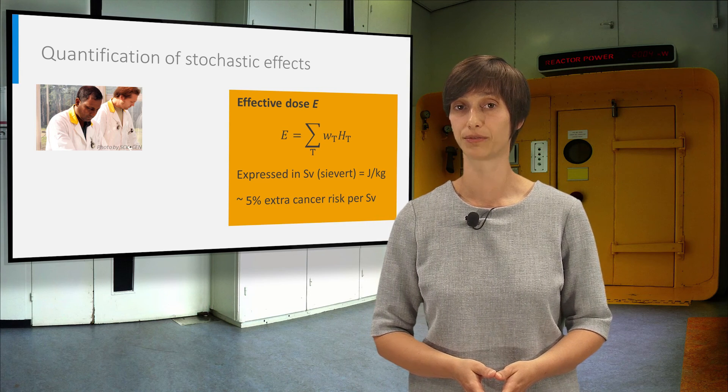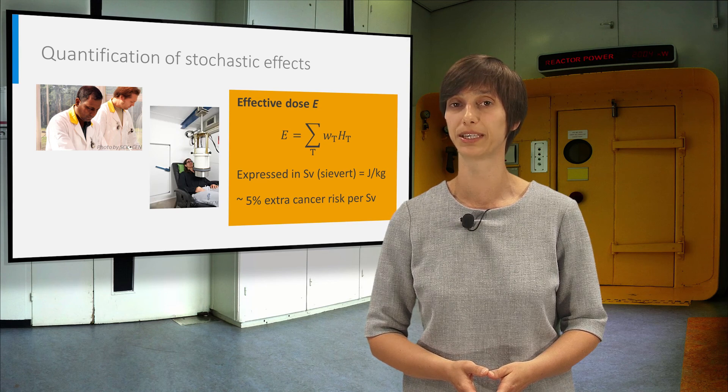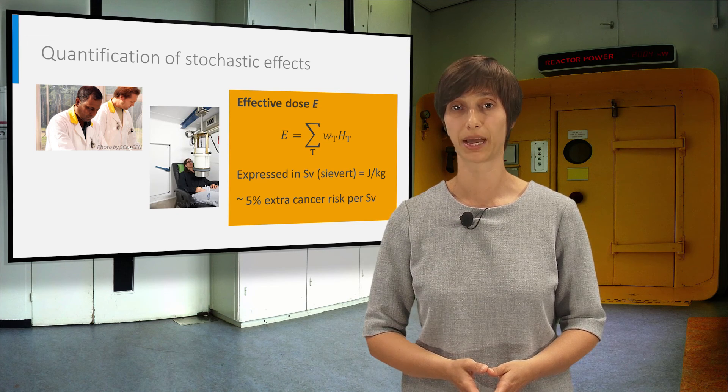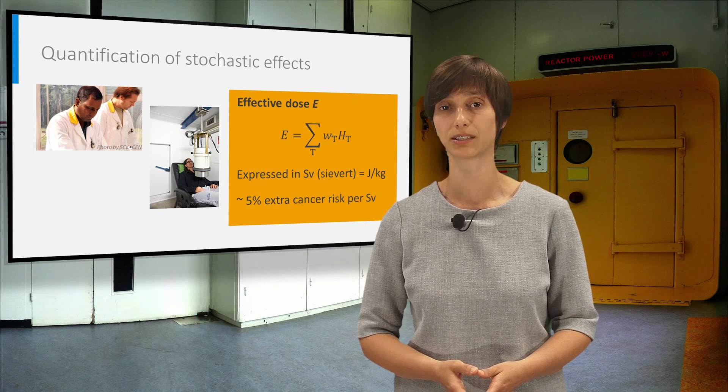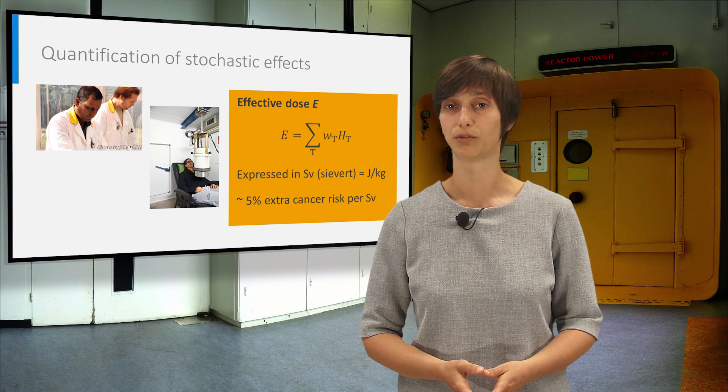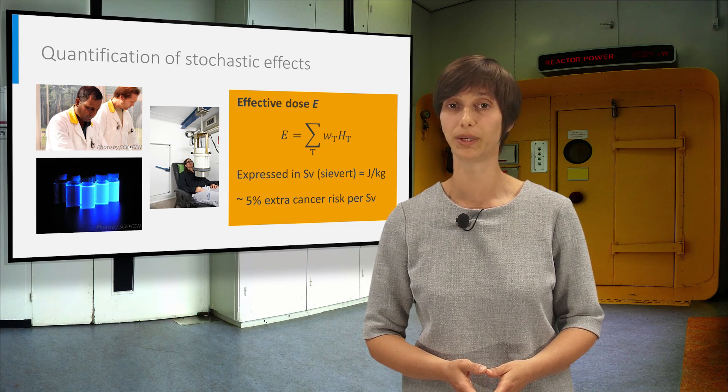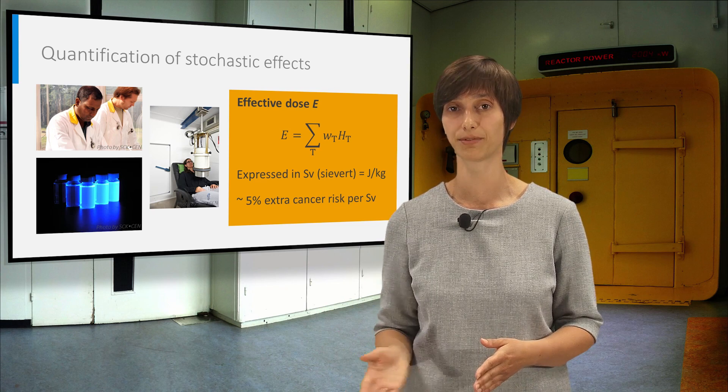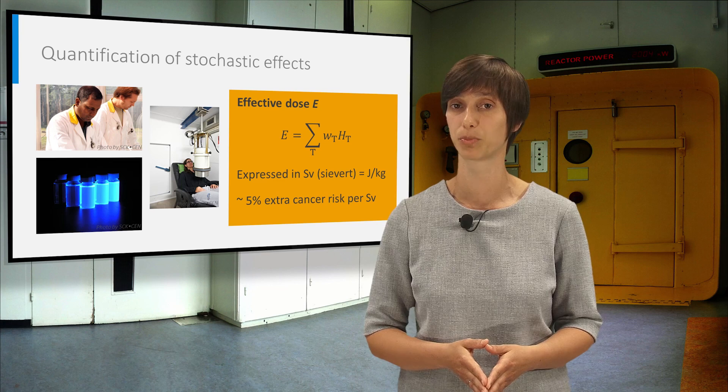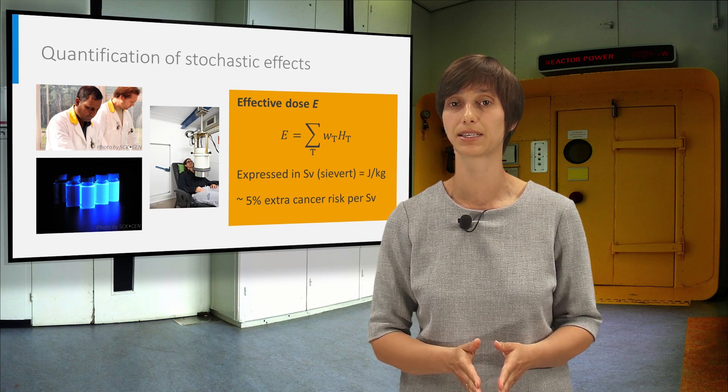Workers at risk of internal contamination with radionuclides also have to be monitored for internal radiation exposure. For gamma emitters, this is done by measurement of the worker with an external detector close to the body. For pure alpha and beta emitters, this is done by dissolving urine samples in scintillation liquid. Such measurements allow calculating the committed effective dose to which the worker will be exposed over the course of his life due to incorporation of radionuclides in his body.